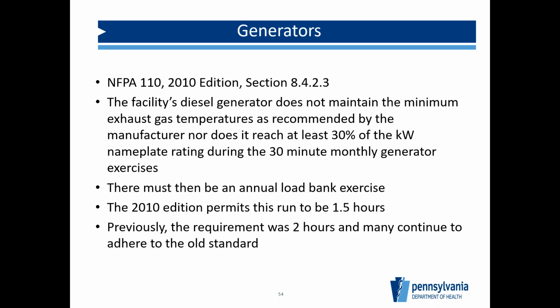you have a couple of options: one, putting more on your generator to get a better load above that 30%, or you can do the annual load bank exercise. But note that if they're still doing 2 hours, you could save yourself some fuel and go to 1.5.